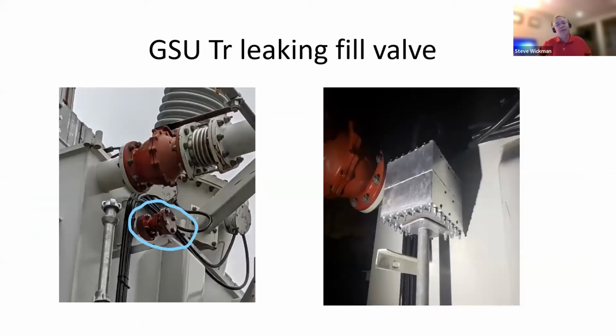Another fun story, back last fall, this is a generating station unit transformer that the prior unit catastrophically failed. And upon putting the replacement unit in place and putting it in service, once that unit got up to rated power and temperature and such, this fill valve here started to leak. And they didn't want to take the unit down for obvious reasons at a power plant to make a traditional repair on that. They would have had to bring the oil level down to do that. They called on us to make a box clamp that we fabricated and designed in an emergency around the clock basis to cover up that fill valve. And you can see the picture on the right there for that repair.